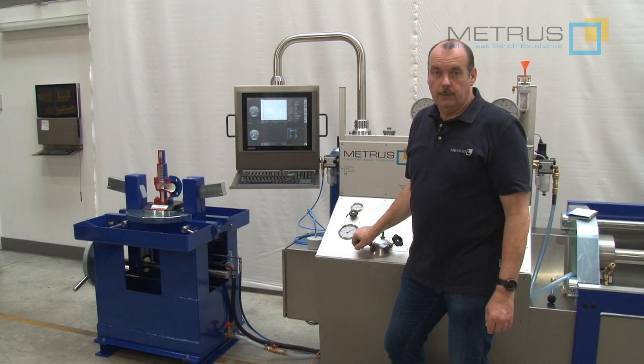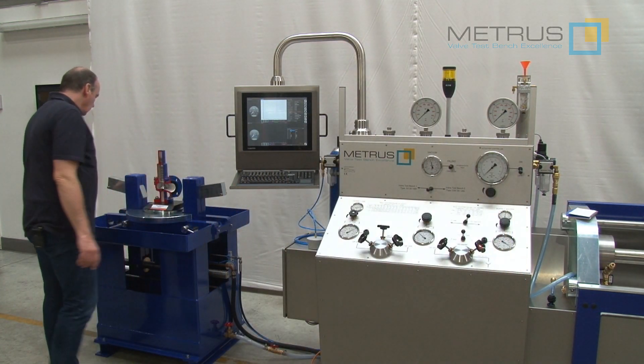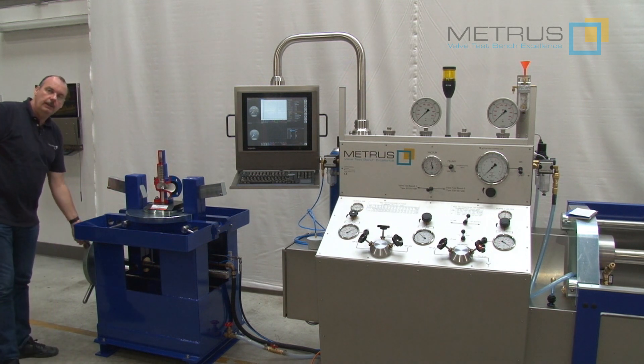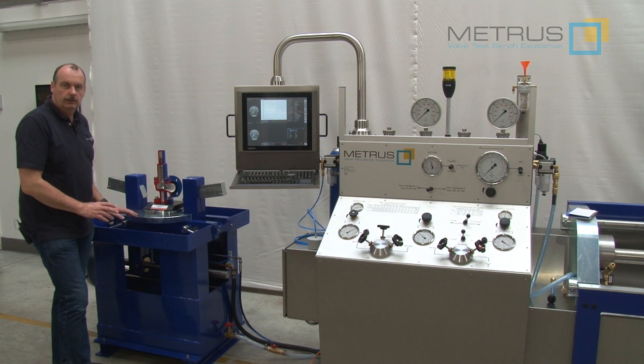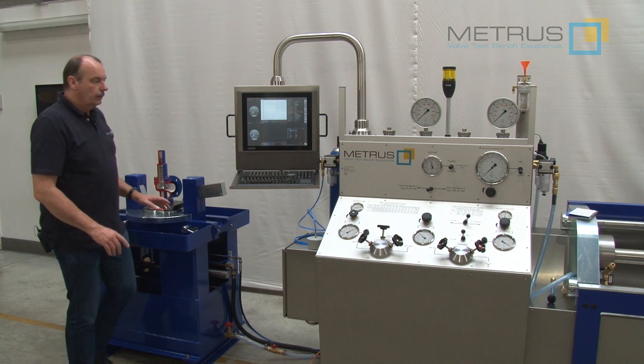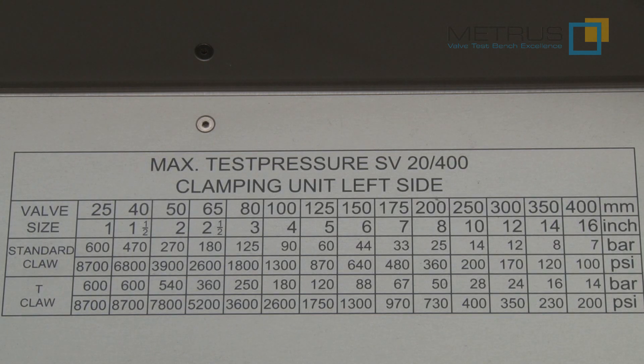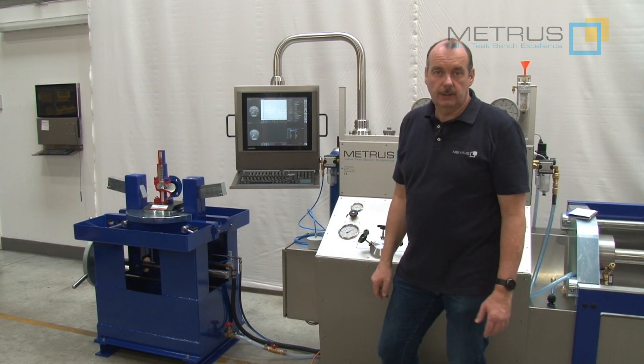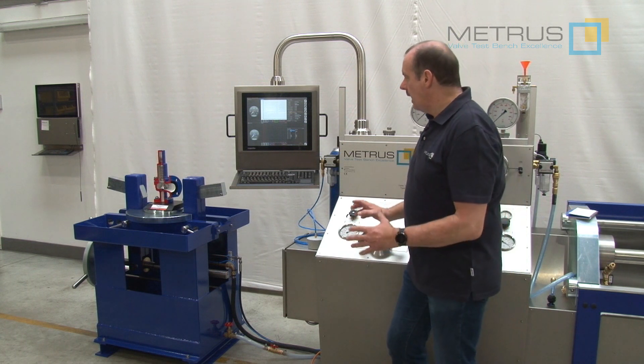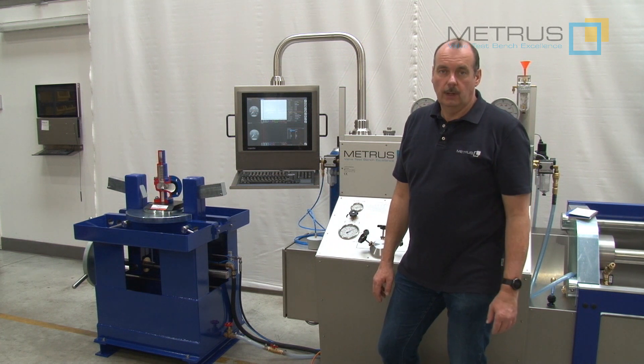Let's start first in testing a safety relief valve on our SV 20/400 clamping unit. Here we have a manual hand clamping which allows us to clamp with a maximum force of 20 tons. On the control panel is shown at which diameter you are still allowed to test with which pressure. As test liquid we can use water with pressures up to 600 bar, or air generated by the air booster and the air accumulator going up to 400 bar.